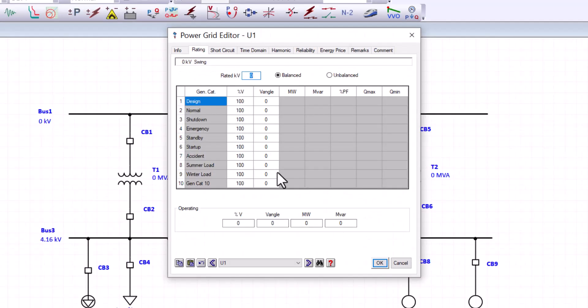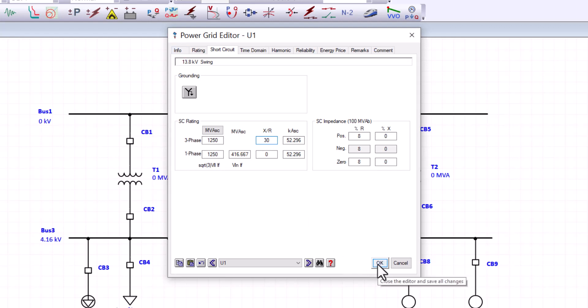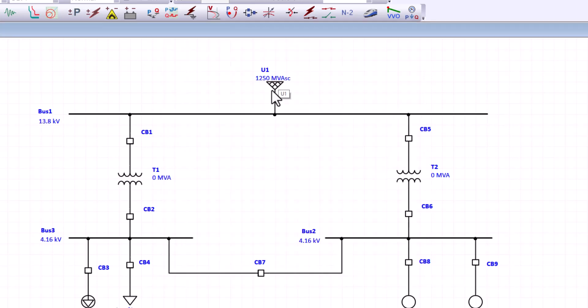And for the rating, we are going to enter 13.8 for this power grid. This is the rated KV. And then for the short circuit, let's enter for the three phase, 1250. And for the X over R, let's enter 30.